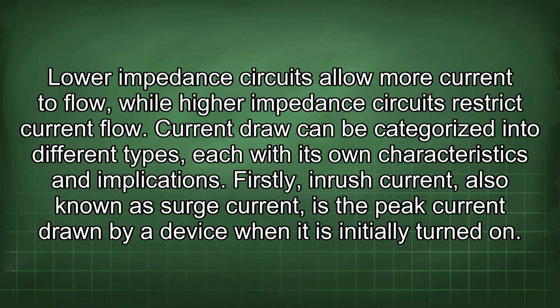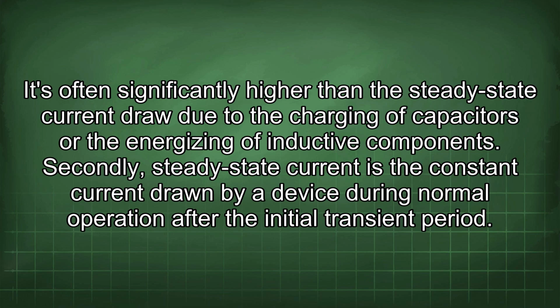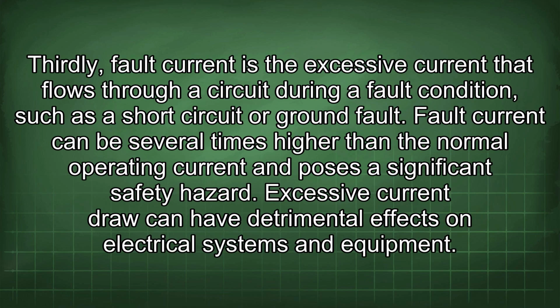Firstly, inrush current, also known as surge current, is the peak current drawn by a device when it is initially turned on. It's often significantly higher than the steady-state current draw due to the charging of capacitors or the energizing of inductive components. Secondly, steady-state current is the constant current drawn by a device during normal operation after the initial transient period. Thirdly, fault current is the excessive current that flows through a circuit during a fault condition, such as a short circuit or ground fault. Fault current can be several times higher than the normal operating current and poses a significant safety hazard.